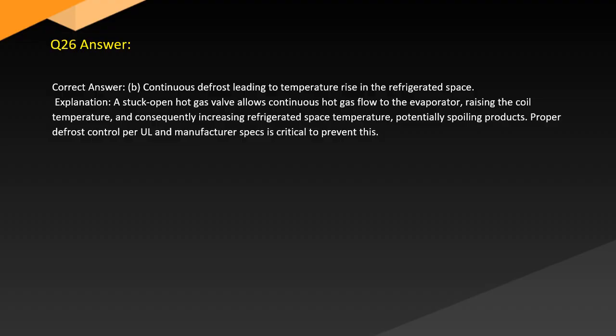Answer. Correct answer: B. Continuous defrost leading to temperature rise in the refrigerated space. Explanation. A stuck open hot gas valve allows continuous hot gas flow to the evaporator, raising the coil temperature and consequently increasing refrigerated space temperature, potentially spoiling products. Proper defrost control per manufacturer specs is critical to prevent this.